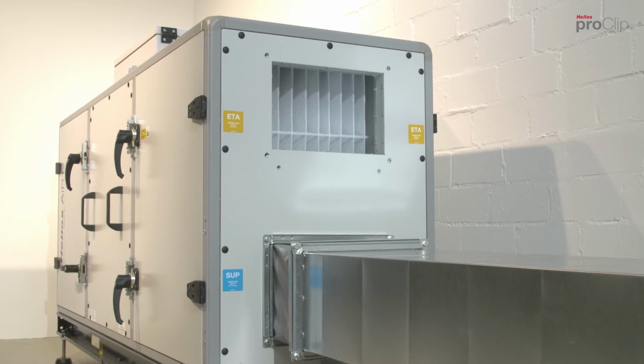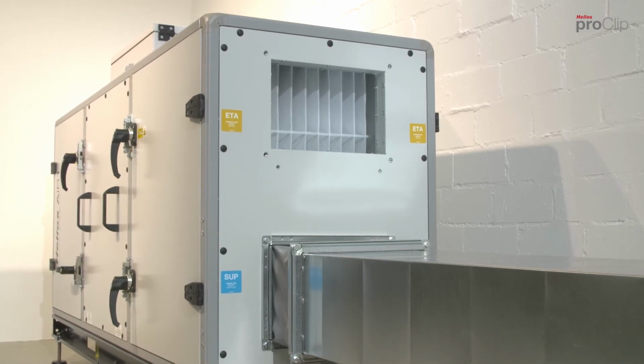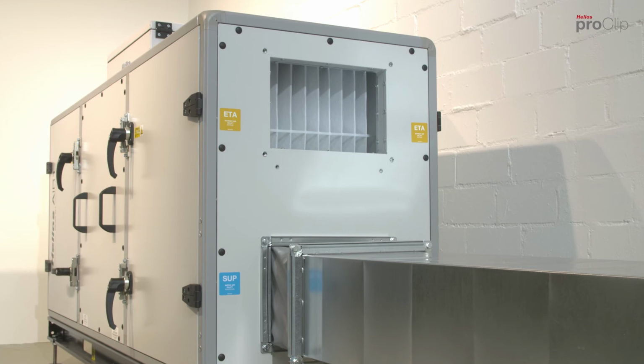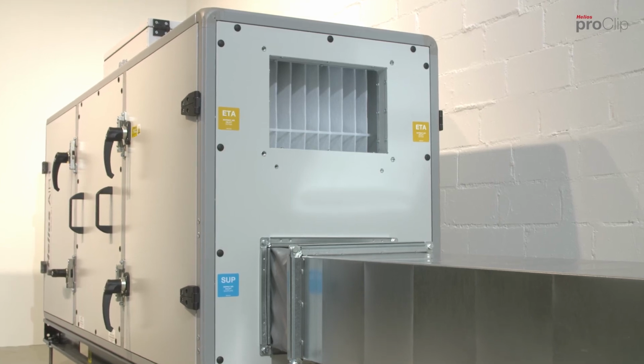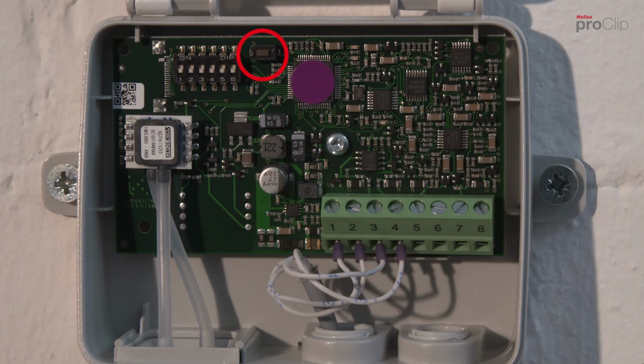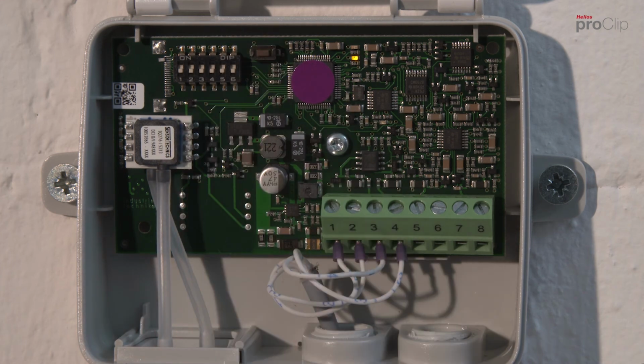The cap pressure sensor must be calibrated before installation is complete. To do this, activate the ventilation unit and wait around 10 minutes. Then press the cap sensor calibration button for a 0 calibration. The calibration is complete when the yellow LED goes out.